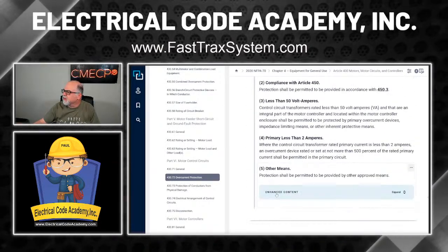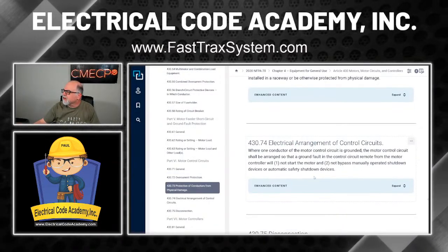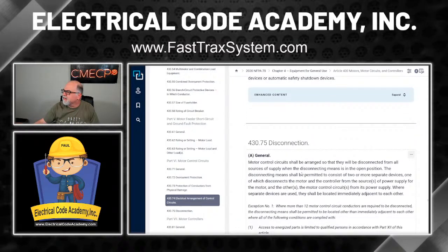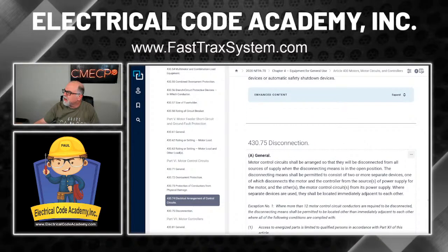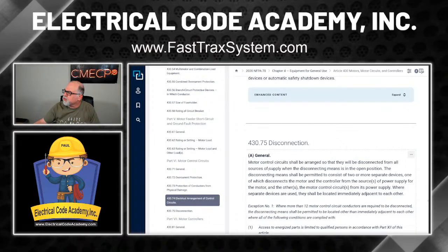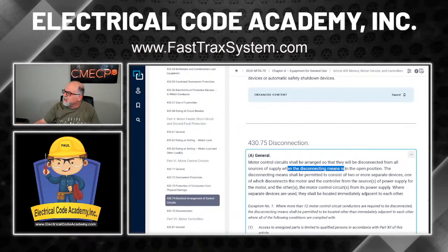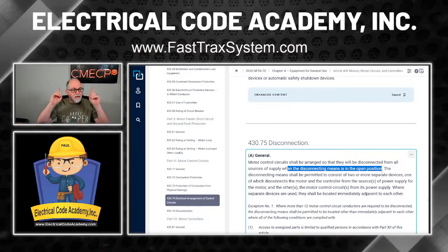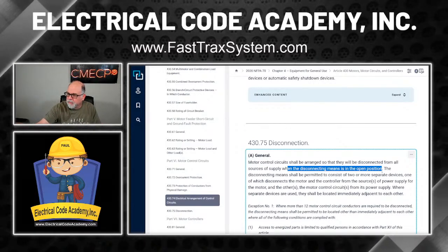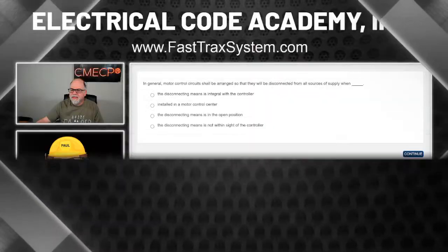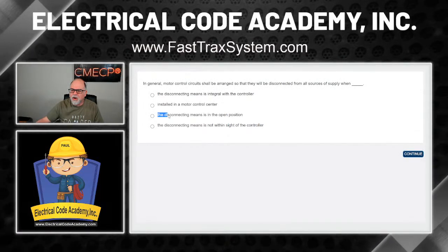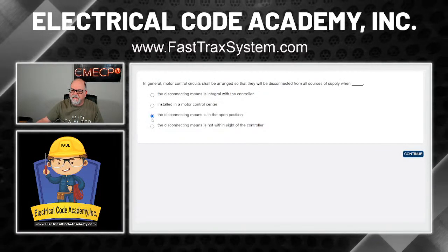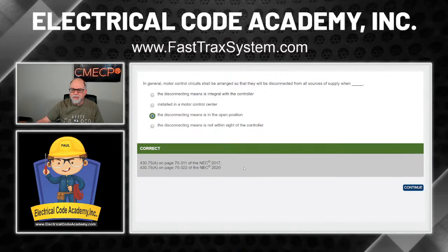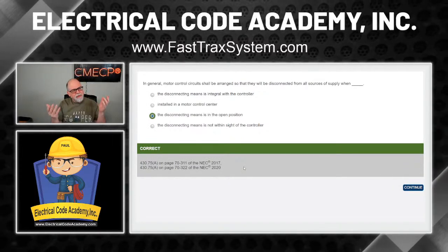And here's control circuit conductors, arrangement of disconnection. Motor control circuits shall be arranged so that they will be disconnected from all sources of supply when the disconnecting means is in the open position. See how we dissected that? Let's come back. Disconnecting means in the open position, right there. That's the answer. Boom. 430.75(A). You see how we did that?